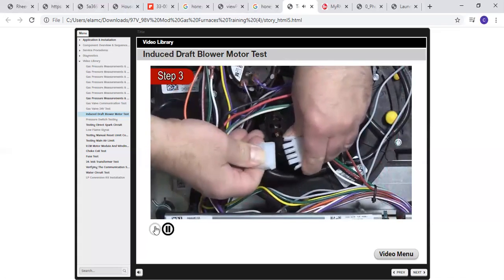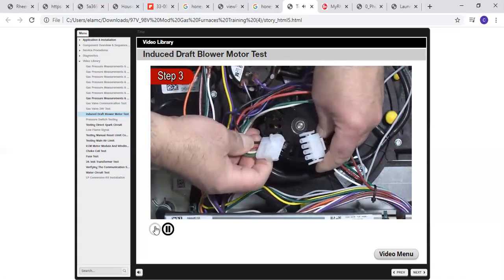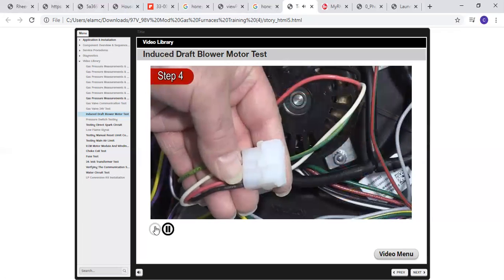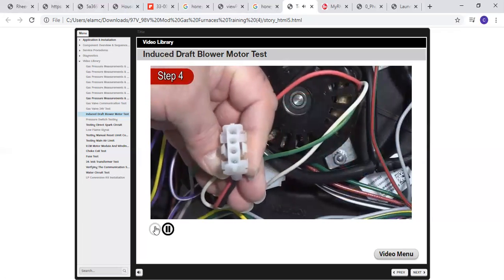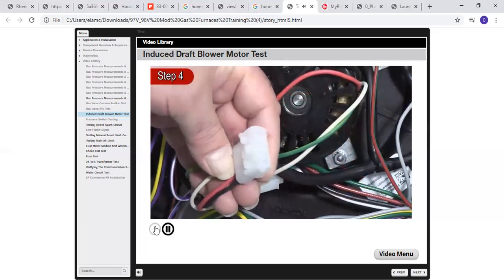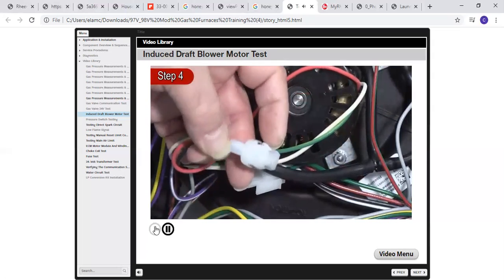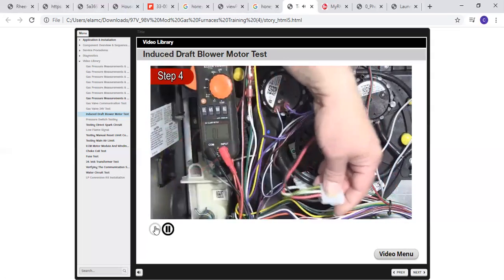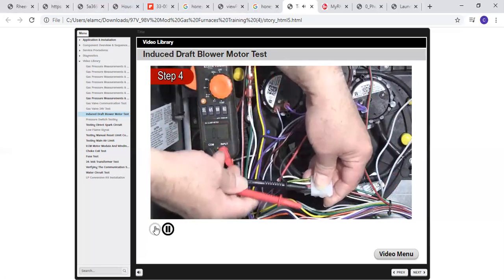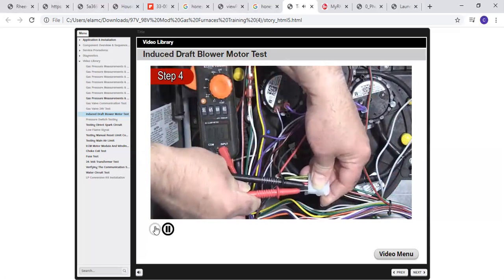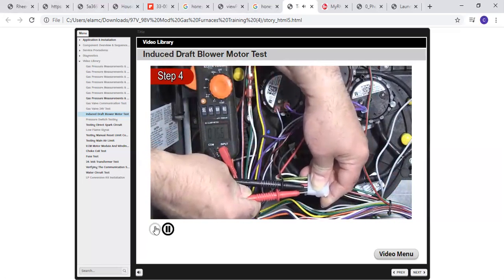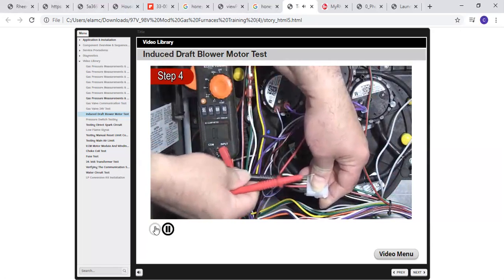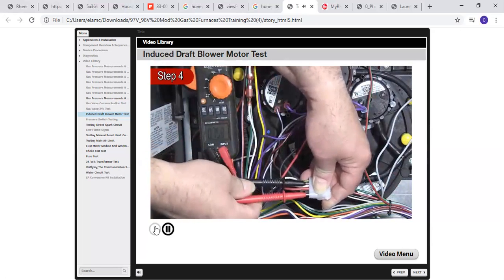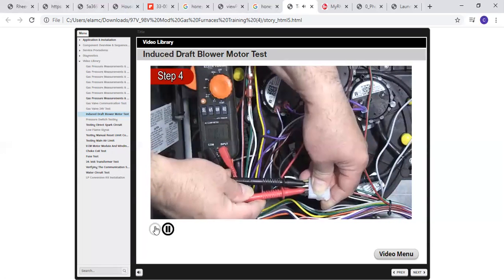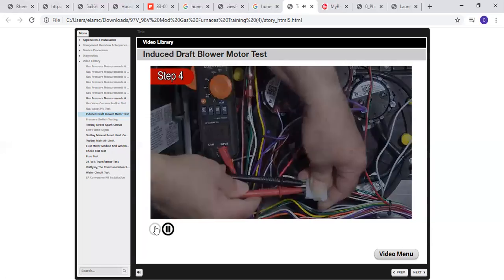Step 3. Unplug the induced draft blower motor wiring harness. Step 4. The motor has 4 wires going to the plug, windings L1, L2, L3, and ground. Using an ohm meter, ohm out all combinations of motor windings, L1 to L2, L1 to L3, and L2 to L3. The resistance measured between all combinations of motor windings should be equal if the motor windings are good.